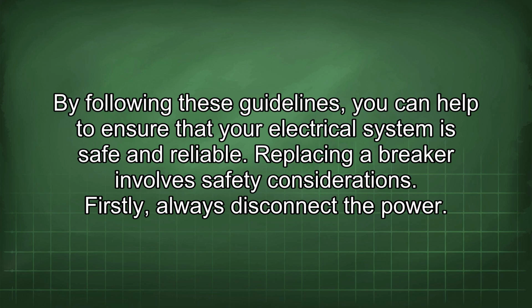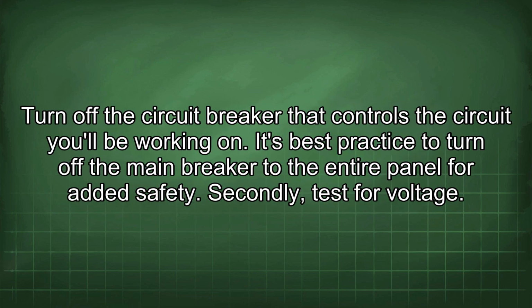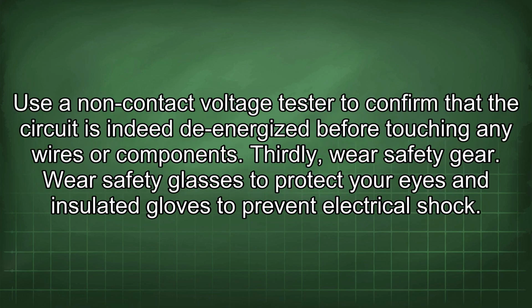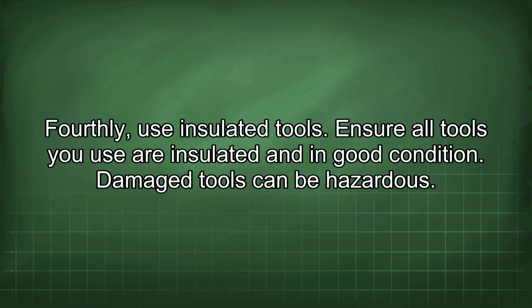Replacing a breaker involves safety considerations. Firstly, always disconnect the power. Turn off the circuit breaker that controls the circuit you'll be working on. It's best practice to turn off the main breaker to the entire panel for added safety. Secondly, test for voltage. Use a non-contact voltage tester to confirm that the circuit is indeed de-energized before touching any wires or components. Thirdly, wear safety gear. Wear safety glasses to protect your eyes and insulated gloves to prevent electrical shock. Fourthly, use insulated tools. Ensure all tools you use are insulated and in good condition. Damaged tools can be hazardous.